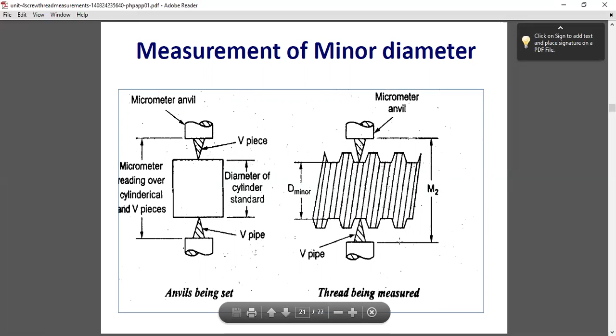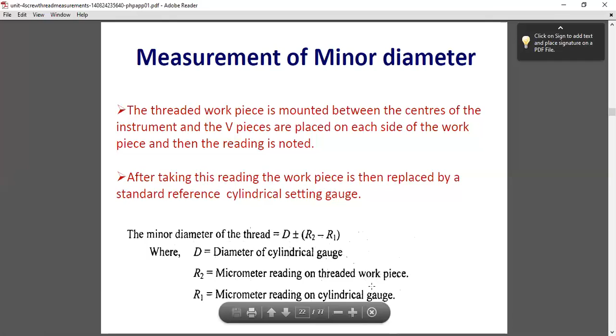After taking this reading, the workpiece is replaced by a standard reference cylindrical setting gauge. Now the minor diameter of the thread is D plus or minus R2 minus R1. D is the diameter of the cylindrical gauge, R2 is the micrometer reading on the threaded workpiece, and R1 is the micrometer reading on the cylindrical gauge.